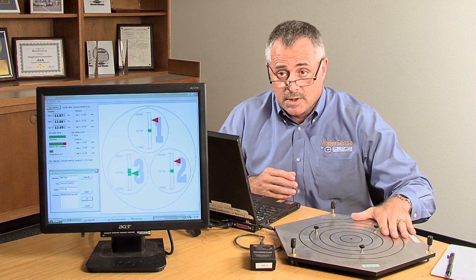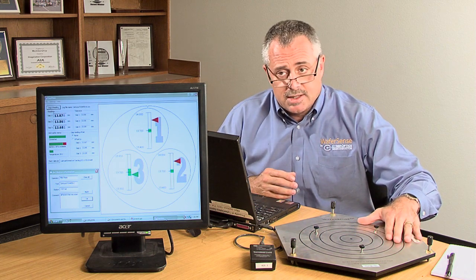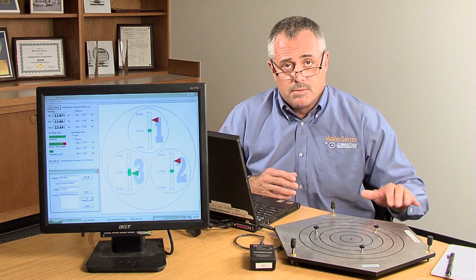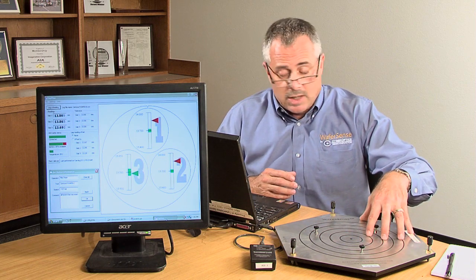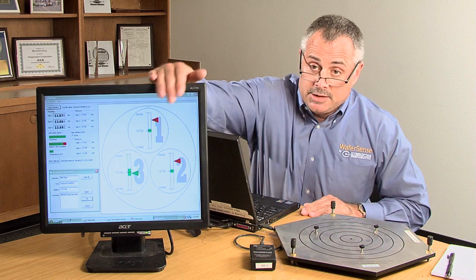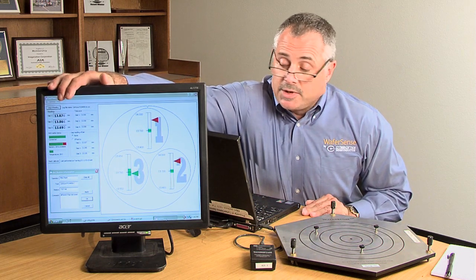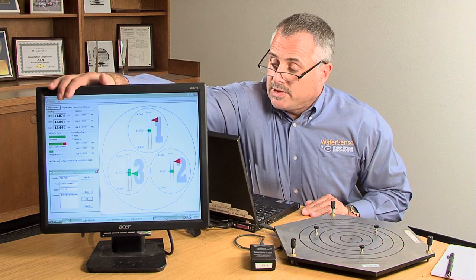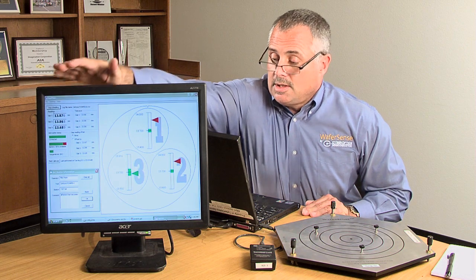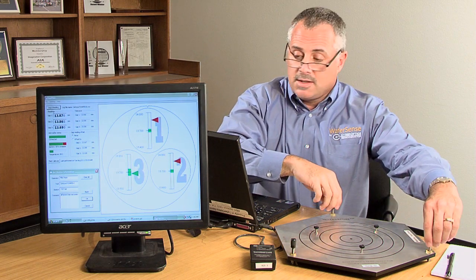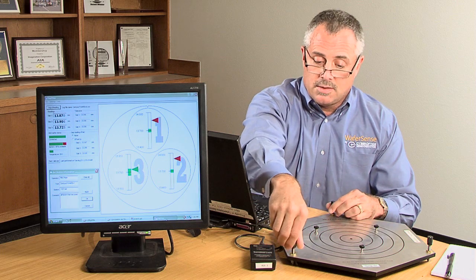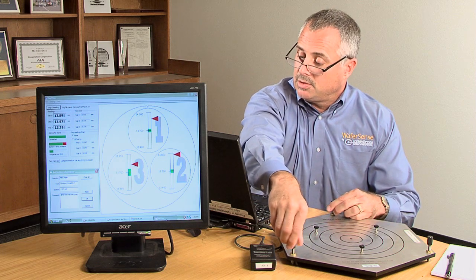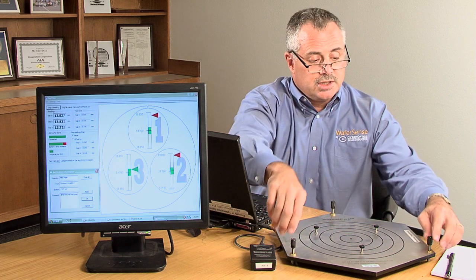So I've placed the AGS under this plate here, which simulates a conductive shower head. And as you can see, there's three distances measured with each of the three sensors. And from there, the technician who's setting up the tool can do the precision gapping.